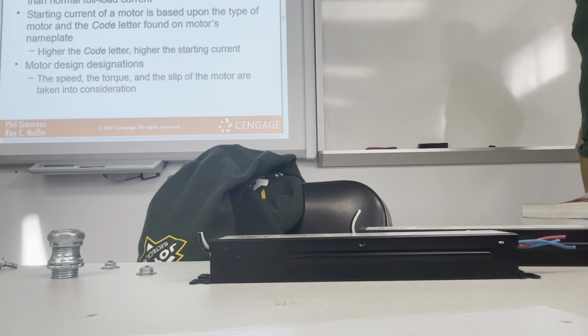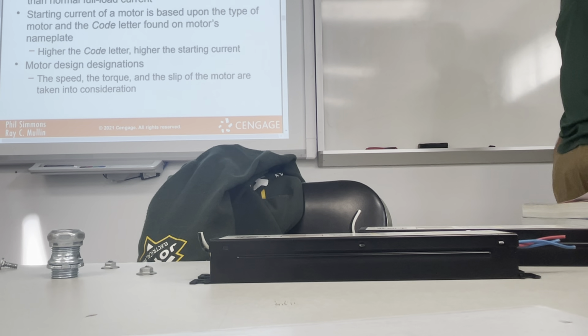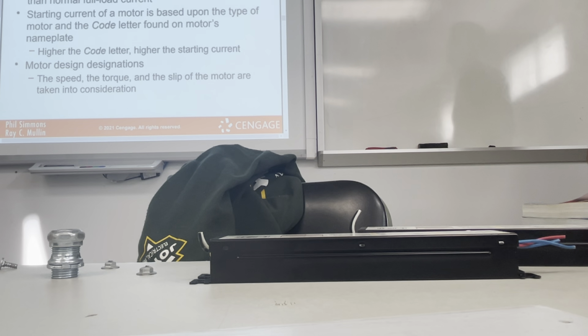Starting current, or locked rotor current, is usually greater than normal full load current. Starting current of a motor is based upon the type of motor and the code letter found on the motor's nameplate. The higher the code letter, the higher the starting current. Motor design designations: the speed, the torque, and the slip of the motor are taken into consideration.